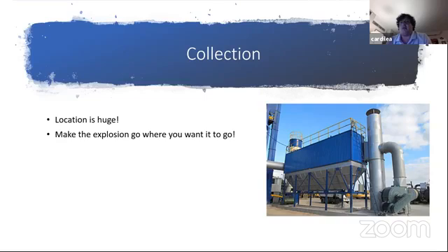accumulation within the site. And sometimes I have situations like they talked about in the CSB video where it's not sized properly, and then you have accumulation. Sometimes operations change, they increase production, stuff like that. So I have to go to these sites oftentimes on an annual basis because conditions change over a period of time, and we have to help them continue to manage that.